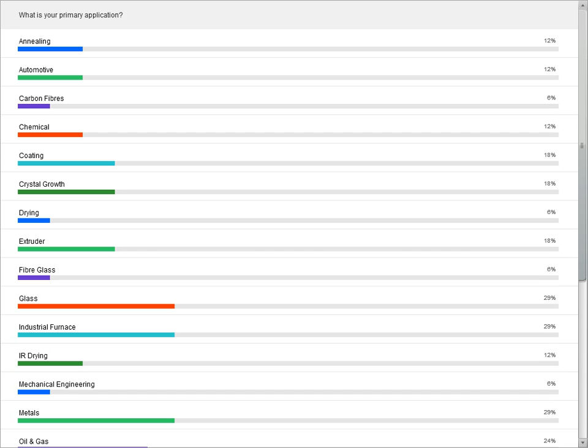So we have a really wide range of current. Thyro-PX is available from 16 amp types up to 2900 amp types. Of course we have single-phase, two-phase, and three-phase units. The two-phase unit is for the three-phase economic circuit. We have precise control of electrical power, current, or voltage, and several operating modes and control modes. There's mains load optimization, which I will talk about later, and the multi-zone feature, which is completely new, so I will talk about that too. Also new is the fuse monitoring and the completely integrated IP20 protection.